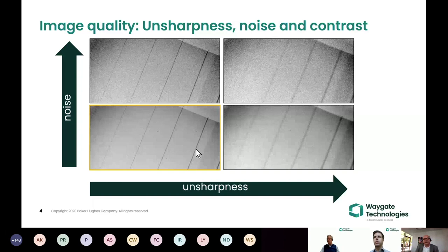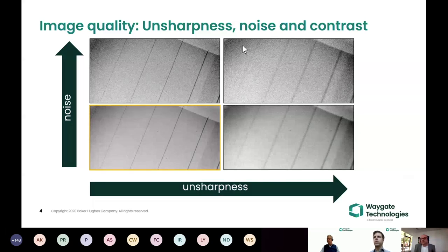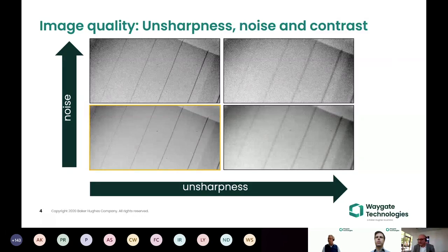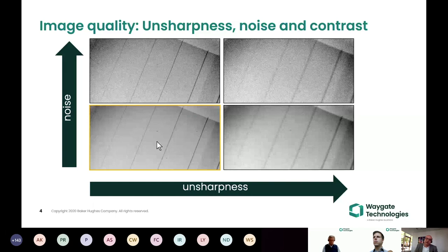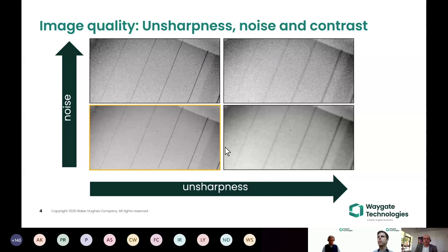You might also notice that this wire looks much darker here than elsewhere, so the contrast is also influenced by sharpness. This means unsharpness, noise, and contrast - the three main things we use to describe image quality - are somehow interconnected. Image quality is not a property of your system alone; it is a property of your image, meaning what object is on the image and under which conditions the image was taken.